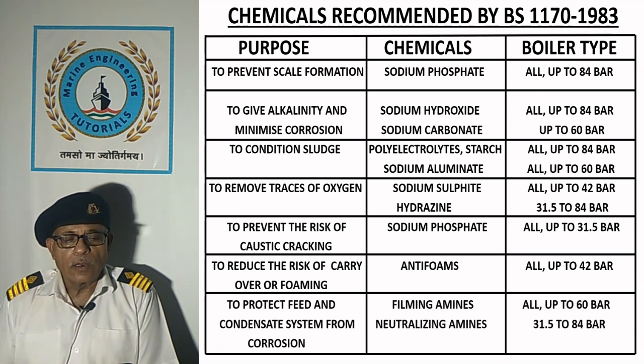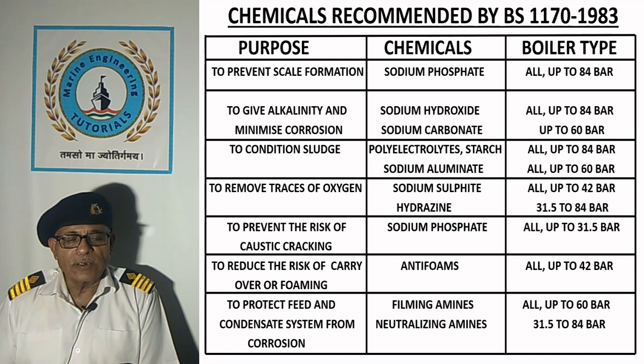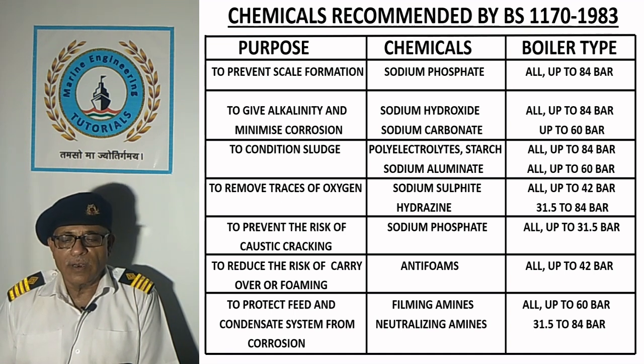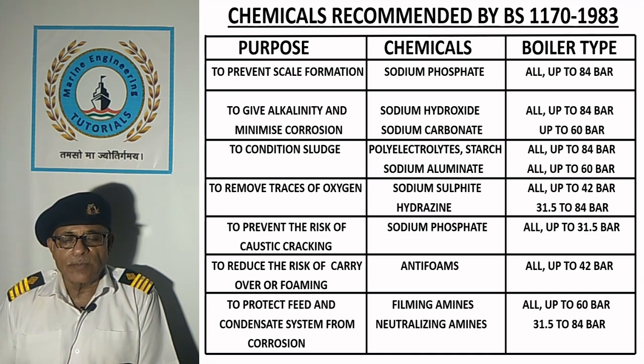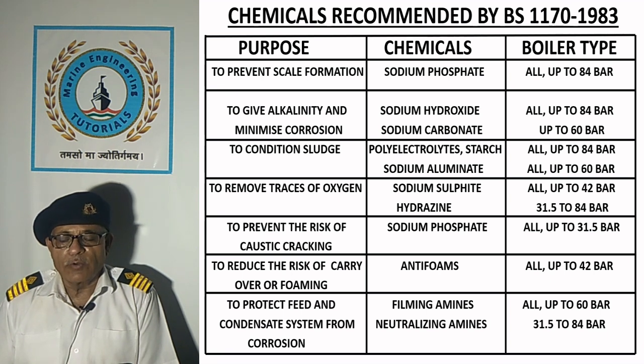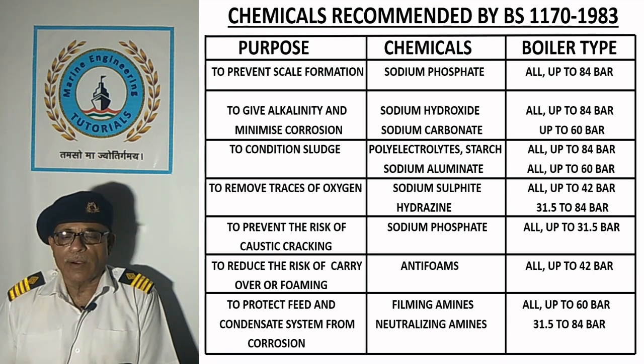To protect the feed and condensate system from corrosion, filming amines can be used for all boilers up to 60 bar, and neutralizing amines for boilers between 31.5 to 84 bar.